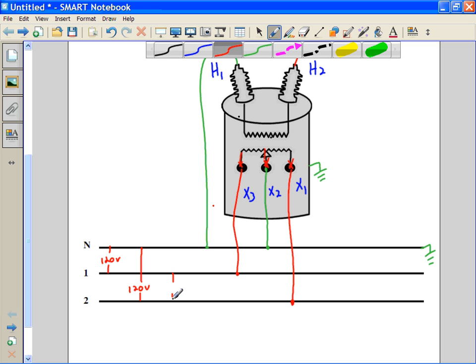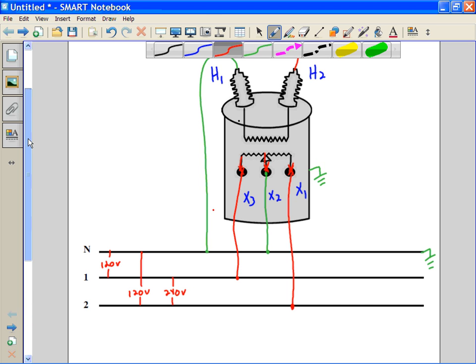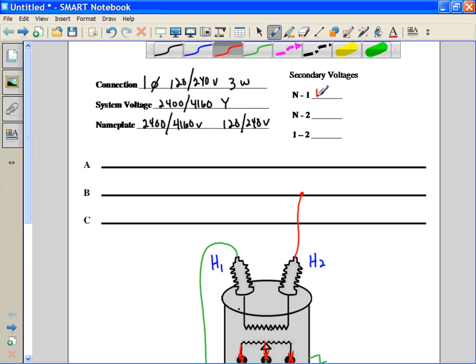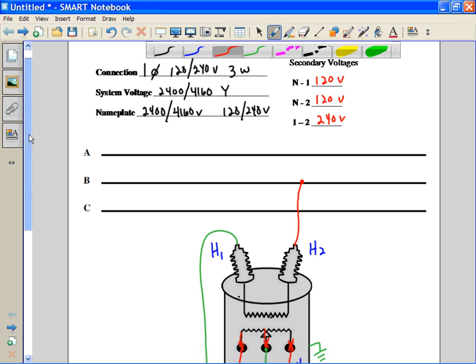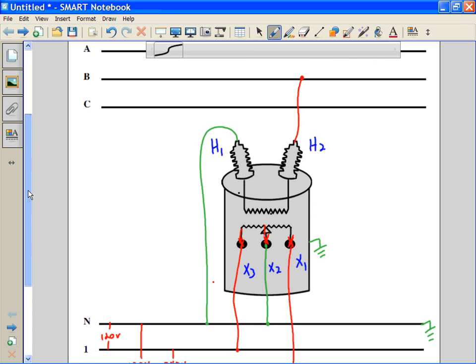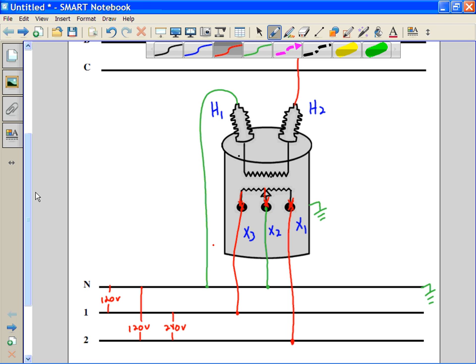And then the voltage between line 1 and line 2, if we follow line 1 back, we get to the X3 bushing. If we follow line 2 back, we get to the X1 bushing. So we are measuring across the entire coil from X1 to X3, and that should be 240 volts. So I always want to fill in those readings wherever the sheet wants you to. Some sheets are going to look different than this one, but there should always be a place where they want you to put the voltages on the secondary side and so forth. Like I say, this is probably the most common single phase connection that you could make.